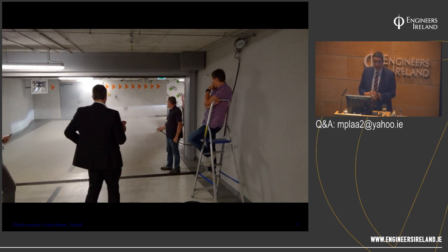So if you come across dry systems, even on sprinkler systems, always ask the question, how long did it take water to get out of the most remote point? Try and do the test. If you're not comfortable doing the test, supervise the test with a competent contractor with your stopwatch and make sure you get water delivery within the allocated time. And it's one of the areas where dry systems in all forms of fire protection commonly fail.